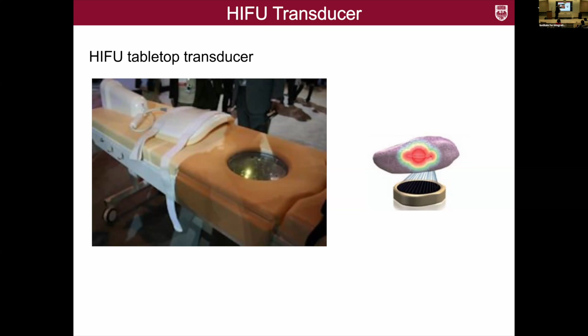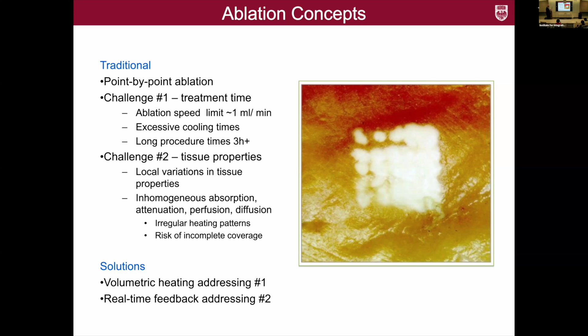Here's a photo of the tabletop transducer again. So this is the MRI patient table. Here's the HIFU transducer, and we can use this for the treatment of the tissue. There are different ways of ablating the tissue. We can do it point by point, which takes a very long time, of course. Or we can use volumetric heating by asking the machine to do a volumetric scan over the area that we are interested in. They have all kinds of advantages and disadvantages. I don't want to go too much into detail, but one of them takes very long. The other one is faster, but is maybe not as precise as the point-by-point treatment.